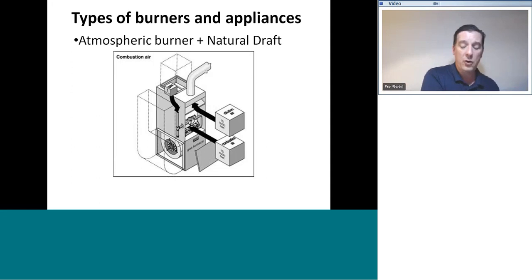We've got a great question here. What causes the negative pressure that draws the exhaust upwards, or draws the flue products up through the flue? What causes that negative draft? And that is a great question. The draft is initially established through a phenomenon called the stack effect.